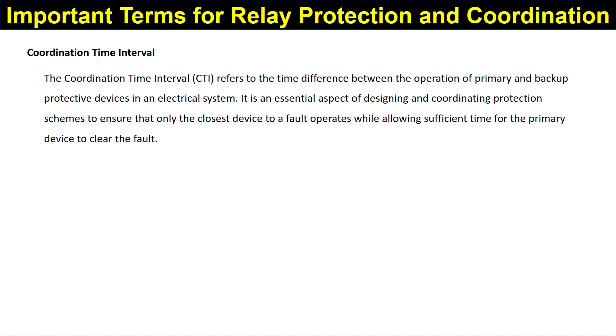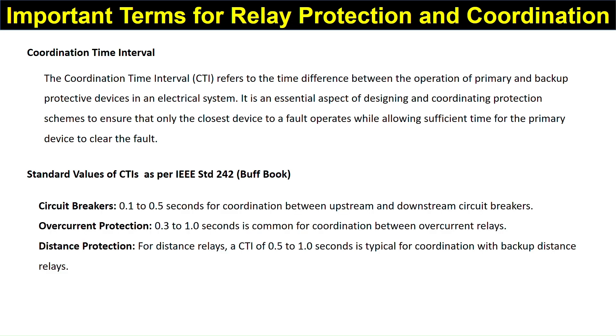Coordination Time Interval, or CTI, refers to the time difference between the operation of primary and backup protective devices. It ensures that only the closest device to a fault operates while allowing sufficient time for the primary device to clear the fault. Standard values as per IEEE Standard 242 (Buff Book): circuit breakers 0.1 to 0.5 seconds; overcurrent protection 0.3 to 1.0 seconds; distance protection 0.5 to 1 second for backup distance relays.